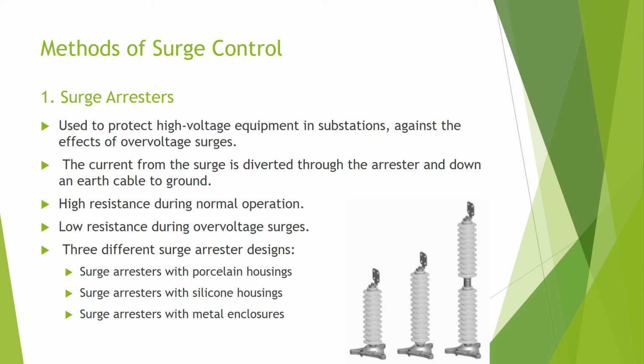One type of surge protection are surge arresters. Surge arresters are used to protect high voltage equipment in substations such as transformers, circuit breakers and bushings against the effects of overvoltage caused by incoming surges. Some overvoltages are very high in energy. The current from the surge is directed through the arrestor and in most cases to earth.